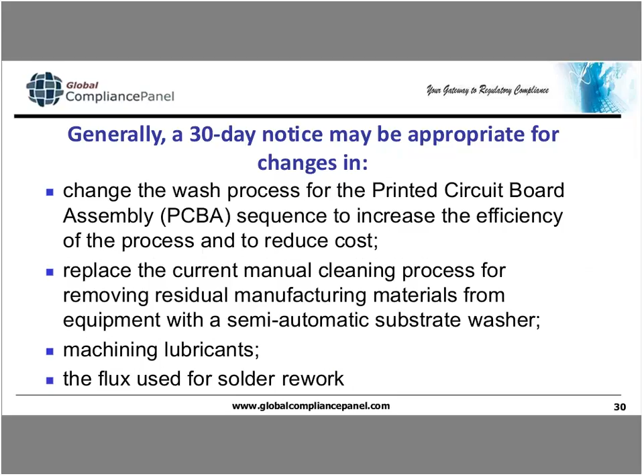In addition, other potential 30-day notice changes include a change that adds a new clean room to an existing manufacturing space, a change from an ISO Class 4 environment to an ISO Class 5 environment, a relocation of a formulation room within a manufacturing facility, using an additional supplier for laser welding of components, adding a raw material supplier, adding an alternate supplier for the UV chromophore for an intraocular lens, and making a change in sterilization test site or sterilization test sample.